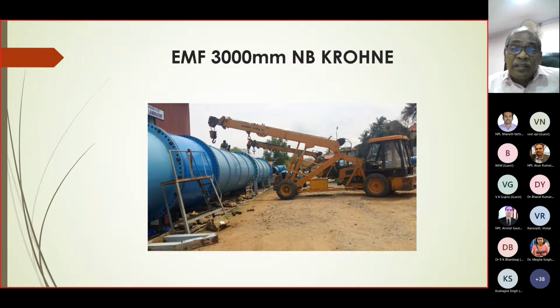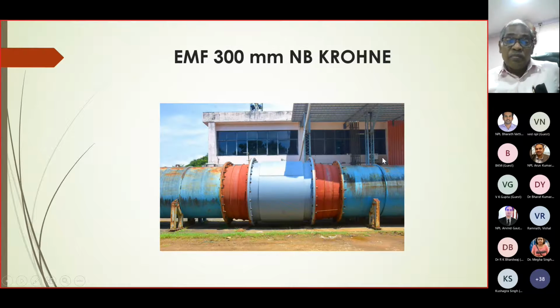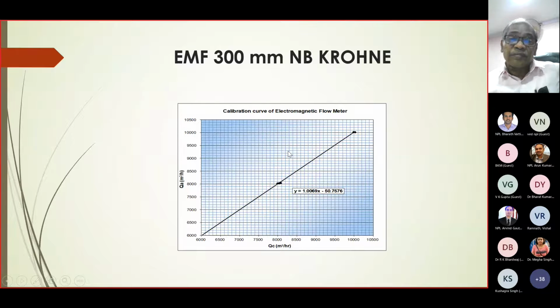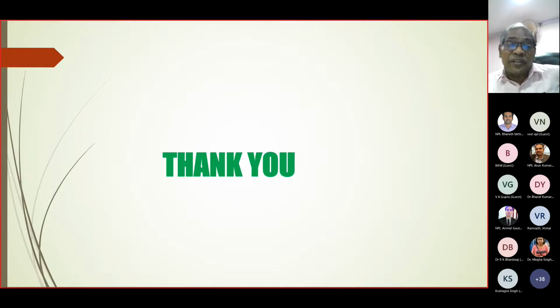Then this is a 3000 mm flow meter for Krohne. For that assembly, we are using 2 cranes. This is another view of the 3000 mm electromagnetic flow meter. 3000, not 300, sorry. This is a calibration curve for the 3000 mm electromagnetic flow meter. They asked to calibrate at a specific point, so 2 points we have taken. The results are very good. Again, the velocity is 0.5 meter per second.